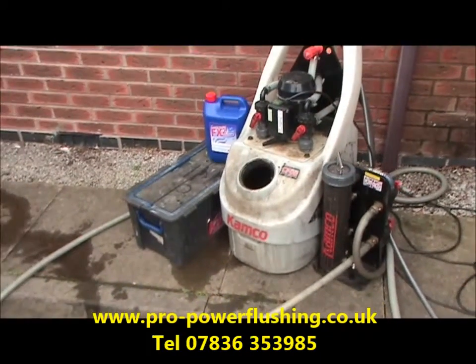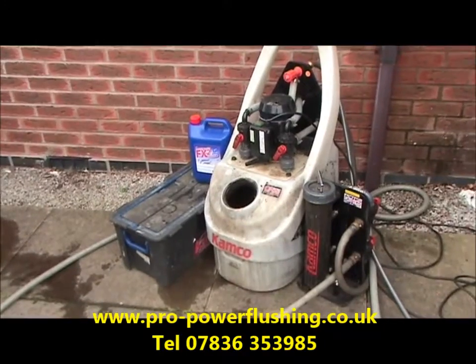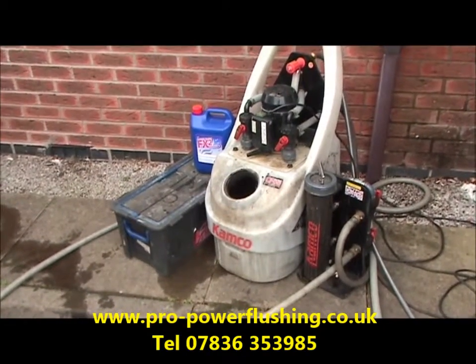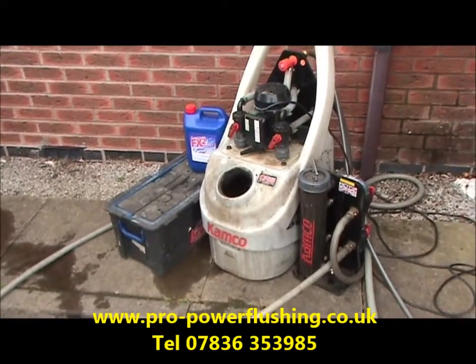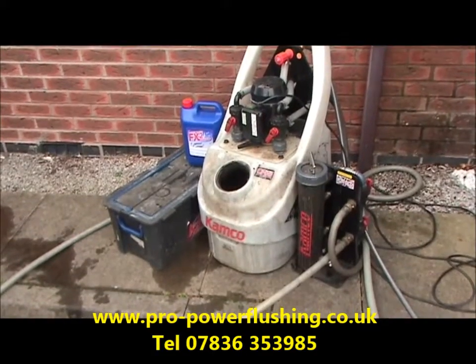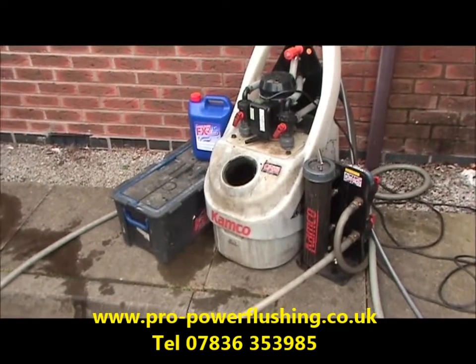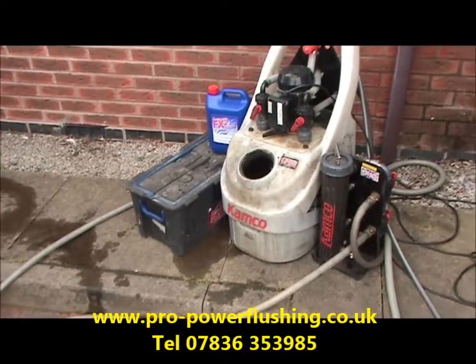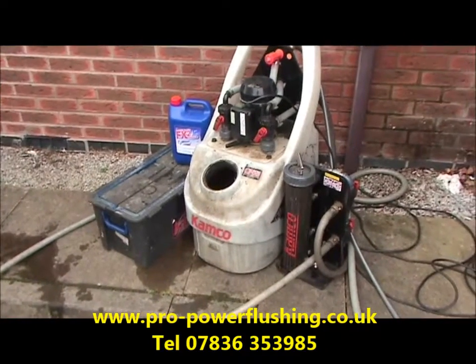We sometimes go to systems that are practically grinding to a halt, and after the power flush the system's up and running like new again, with nice free pipes, free boilers, and heat exchangers freed up, all the rust and corrosion flushed out of the system.